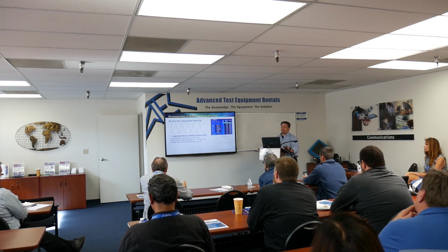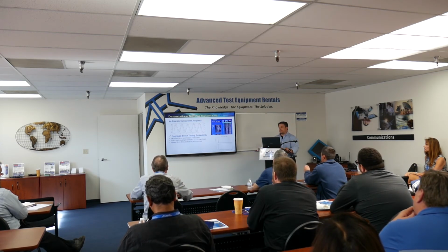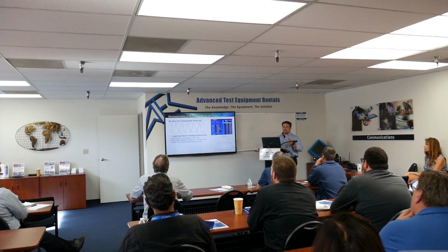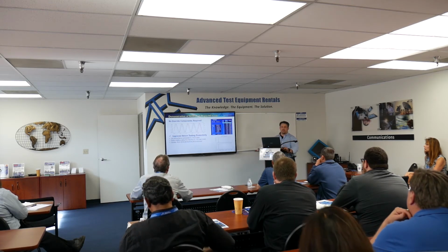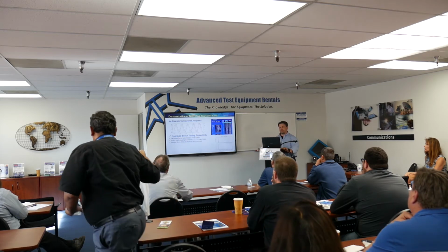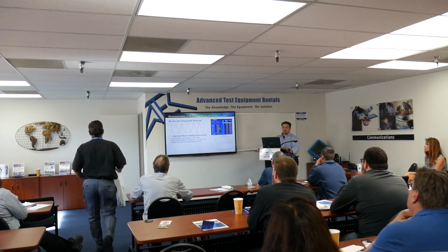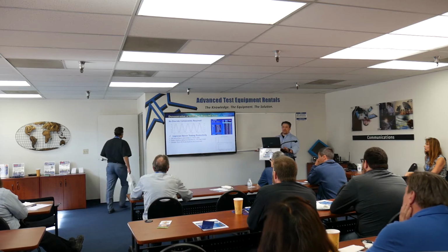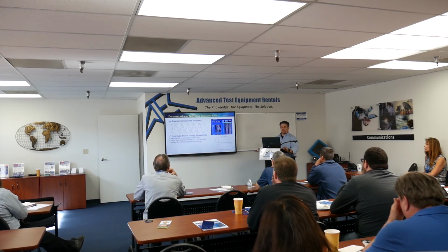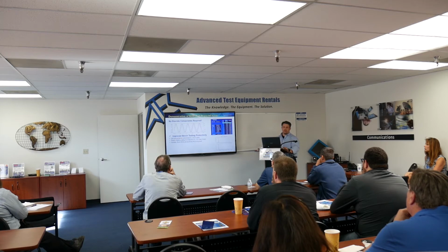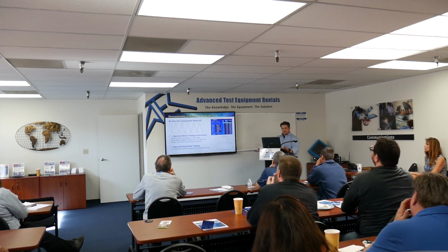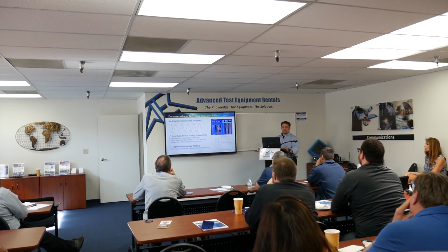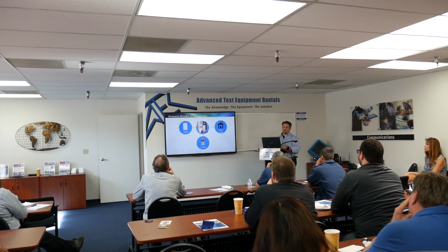And for example, this particular customer was doing this testing, and in the past they were using a load with a big fixture with a bunch of inductors and a bunch of capacitors on the output to give them this inductive or capacitive shift. And by being able to use the 9430, they were able to completely simplify that testing. It really reduced the test time. And also all the added extra components, the relays for switching in this fixture.